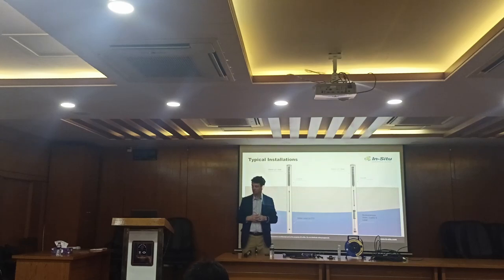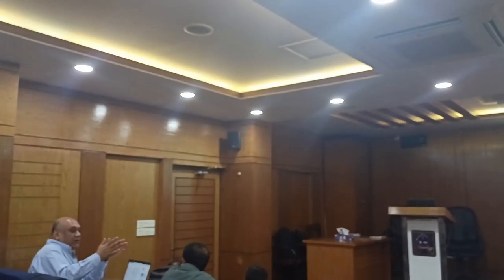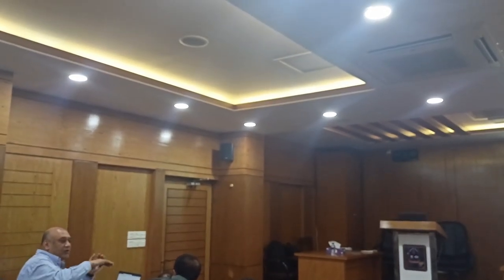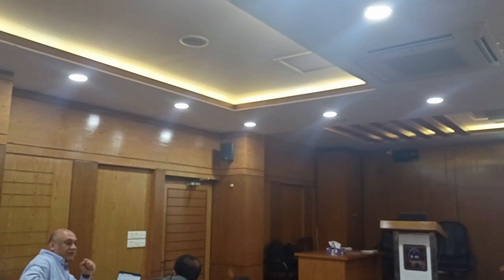Maybe we can add something—sure, just a general rule of thumb. I'm a sales guy, so I tell people: when you see huge changes at your location, say after one or two months, where the data is going all over the place, that's time to do a calibration. Either impurities are affecting it, or there's some sensor challenge—that's the easy way to think about when to calibrate. As was mentioned, every company or institute has their own calibration protocol. If I go to a new site, I'd prefer to calibrate once, because we don't know who used it earlier or what condition it's coming from. So it all depends.